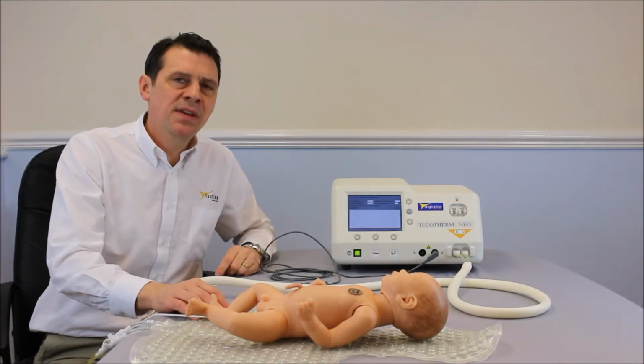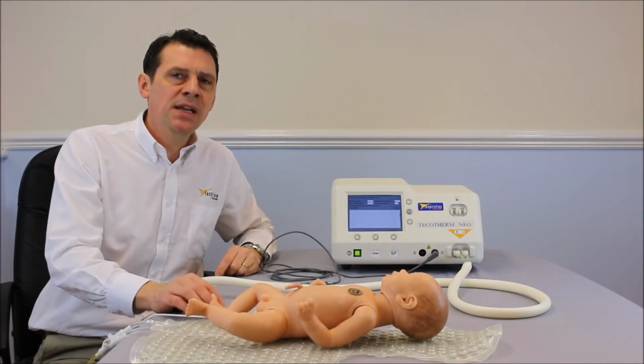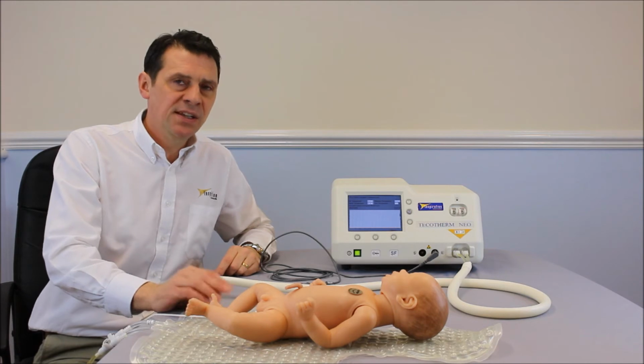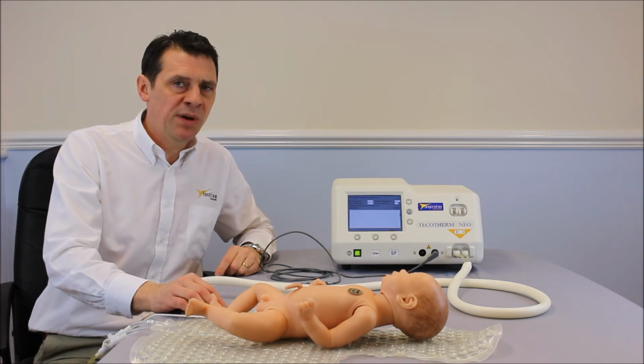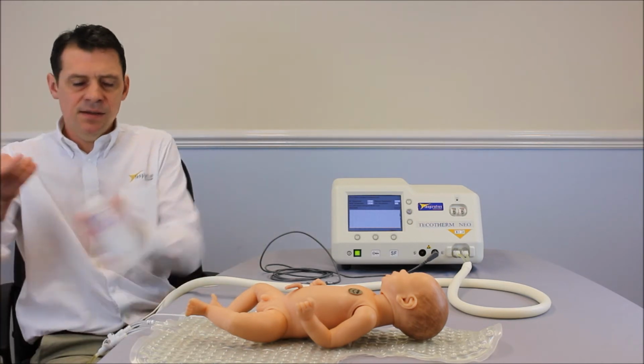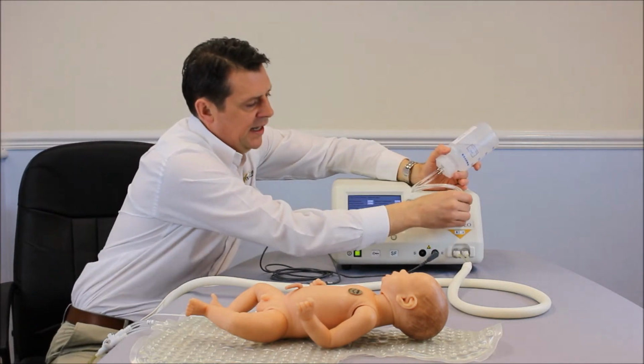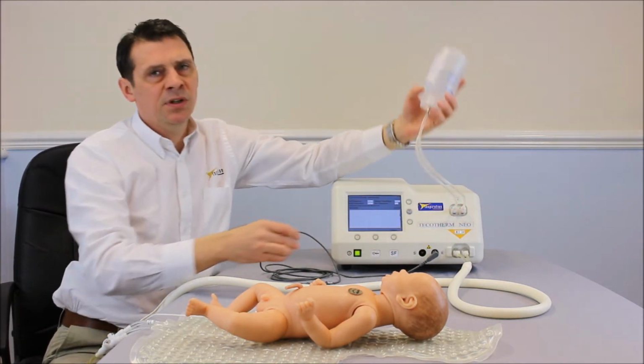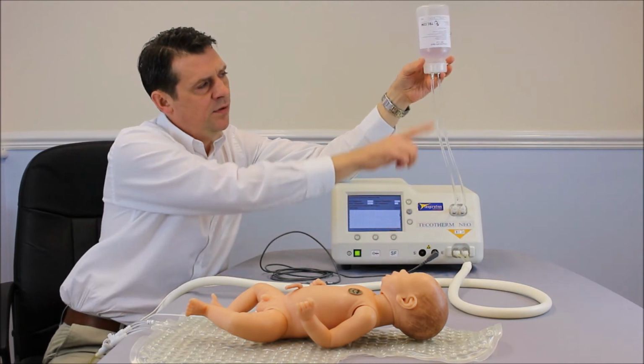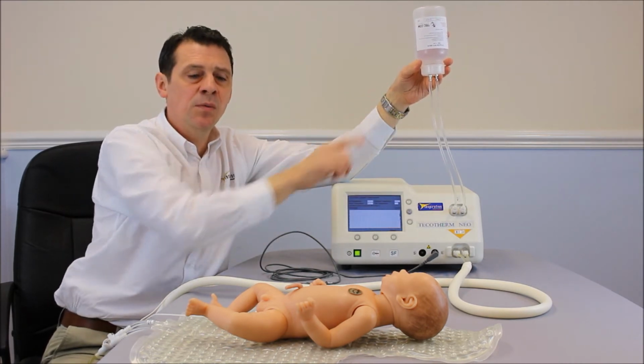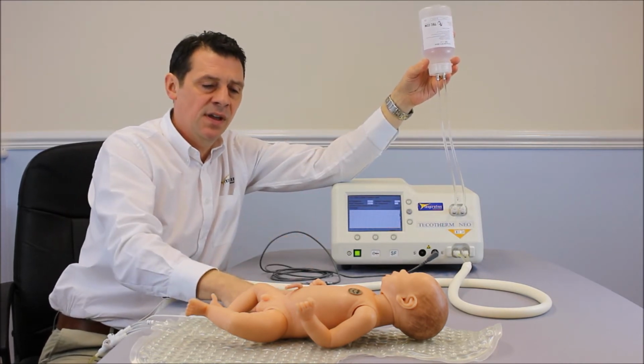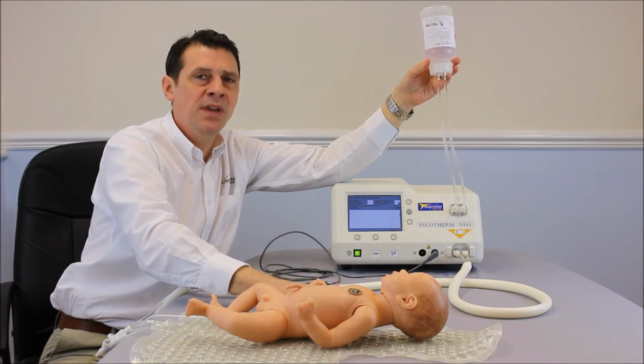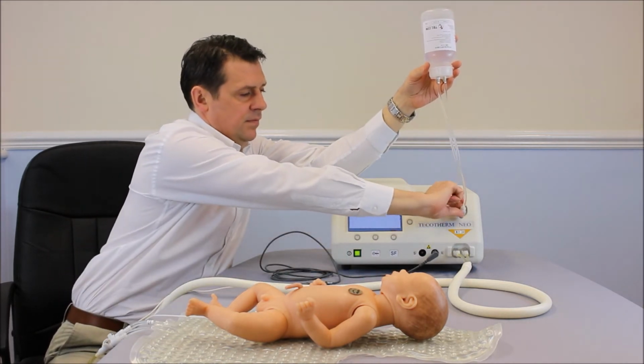It's important to remember that these mattresses are semi-permeable, and over time the liquid can dissipate away and evaporate. We need to top that up, maybe once a shift as good practice. To do that again, same process as we did with the filling. Attach the bottle to both sides, and what we're looking for is when the air bubbles stop coming into the bottle, that we know that we've optimally filled the mattress. Have a feel to test to make sure you're happy with that, and then disconnect.